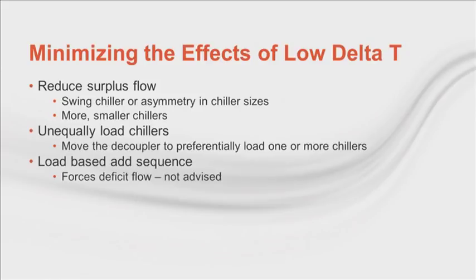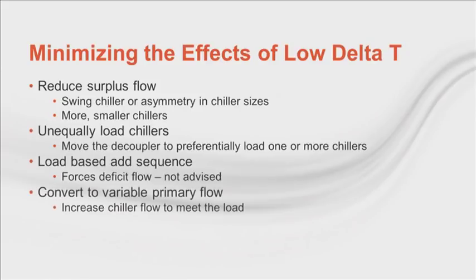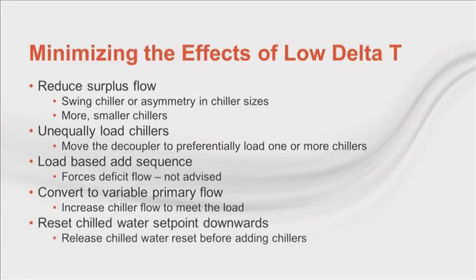To reduce the number of chillers online, convert to variable primary flow. Put a variable speed drive on the chiller pump and change the water flow rate to meet the load. And then the least disruptive change is to keep the decoupler, but change to variable primary, variable secondary, and match primary and secondary flow. I'll discuss this in a few minutes. So this restores some of the missing chiller capacity, reduces the number of chillers operating, and the amount of surplus flow. However, it does not resolve low building DeltaT. Another way to deal with the chiller capacity loss is to release chilled water reset if it's active, or lower the chiller set point.